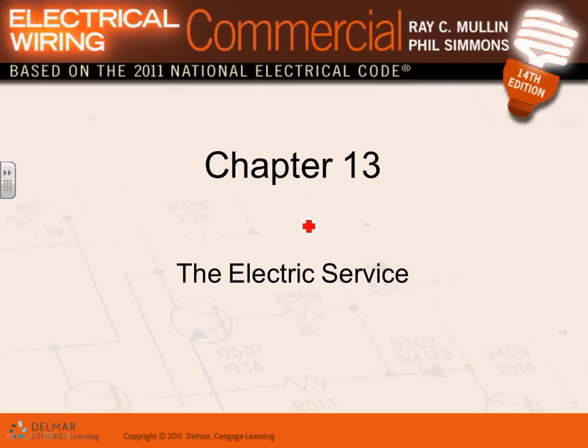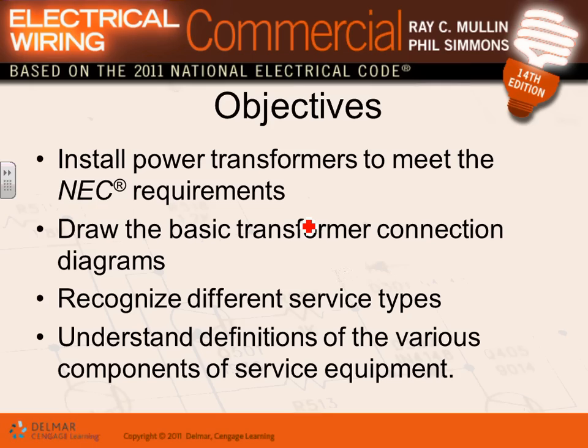You guys have designed it for me. You put it in the building, the commercial building. You put it in the residential building, and you will do it in the industrial building in the spring too. So that's what this topic is. A couple of things about the service equipment. The service equipment, guys, always starts with bringing the power from the utility using a transformer. So we'll talk a little bit about the transformers. Basic connection of the transformers.